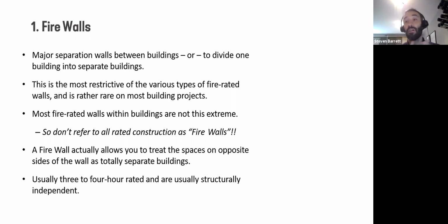So they can have 2 different construction types. They can have 2 different calculations in terms of allowable heights and areas of the building. It's basically 2 separate buildings. Why they're extreme is because firewalls are typically 3 or 4 hour rated, which is really high, and they're structurally independent. So either the wall itself is independent, not tied to either building, or you may have 2 back-to-back walls that are tied to their respective buildings. But it's constructed in such a way that one building could completely collapse and the other building will stay standing. That's how extreme a firewall is.